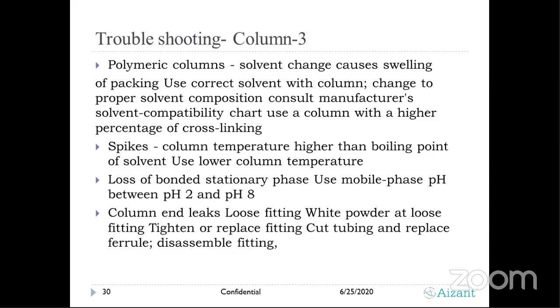I think this point we have also discussed: if there is a recommendation of pH 2 and pH 8, never use the boundaries or extremes of these pHs. Always be minus 1. If pH 2, go with 2.5 or 3. For pH 8, in this case also I recommend using pH 7, not at the borderline of pH 8.1 or 8.2. You will lose the column.